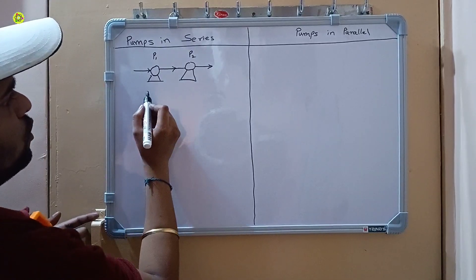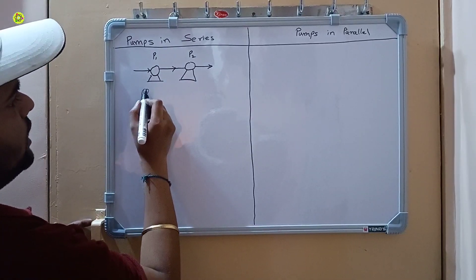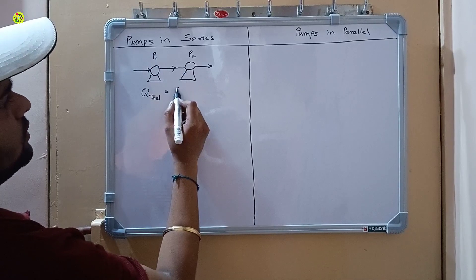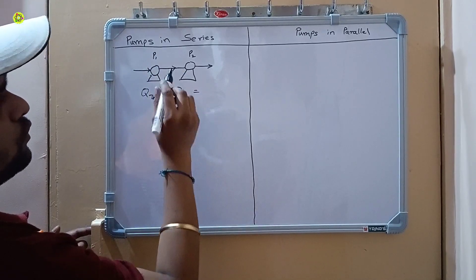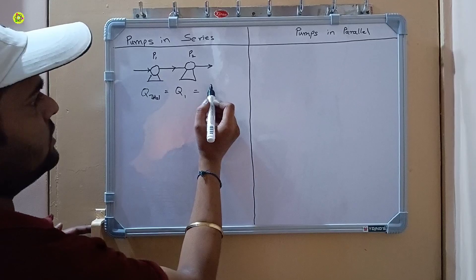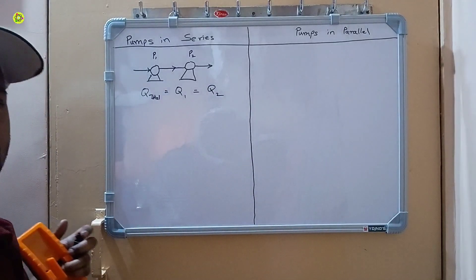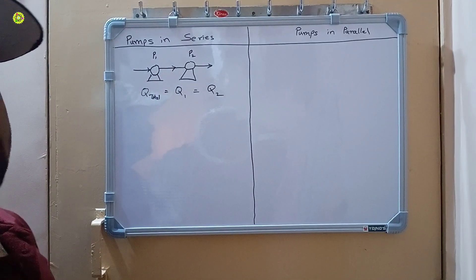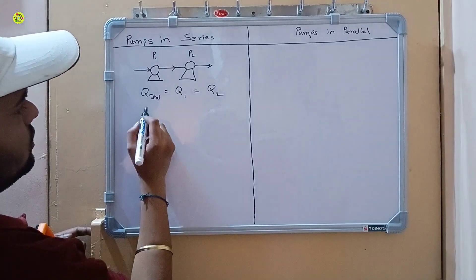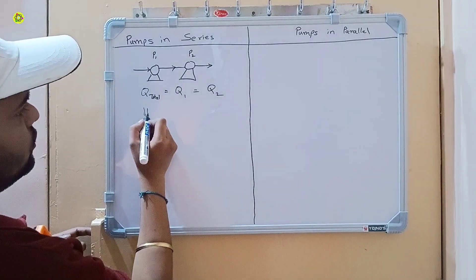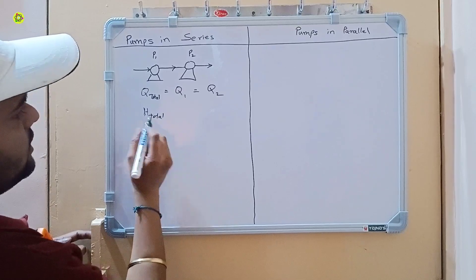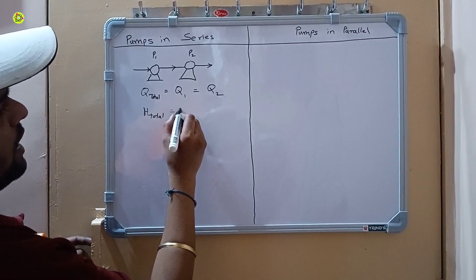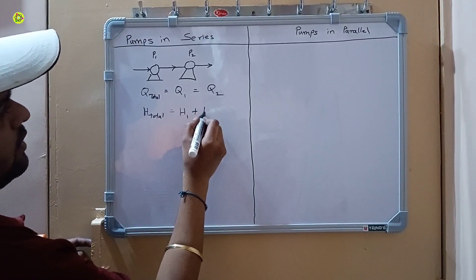In the series arrangement, the flow rate Q is constant: Q total equals Q1, which equals Q2. Because of this series arrangement, we get a higher head. H total equals H1 plus H2.